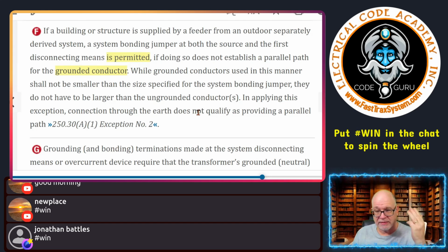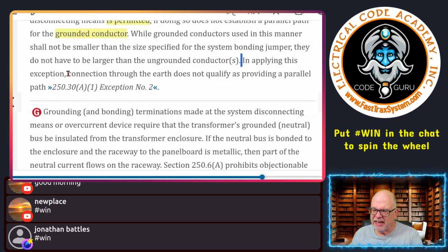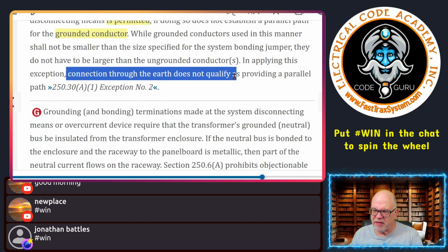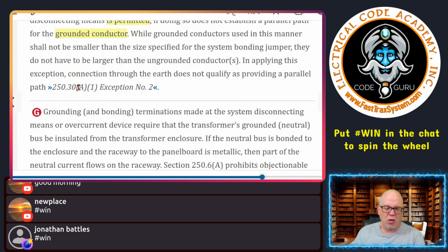ungrounded conductor. Now, in applying this exception, connections to the earth do not qualify as providing a parallel path. Absolutely not. Never would we use the earth as a path at all. So again, make sure you're fully clear on that. The earth is never a path. Now, utility folks, yeah, they can use the earth, because their overcurrent protective devices are so much smaller and the voltage is so much higher. Doing Ohm's law will tell you that it will be fine. But for our case, it's not going to work, right? So we can't use the earth for that.